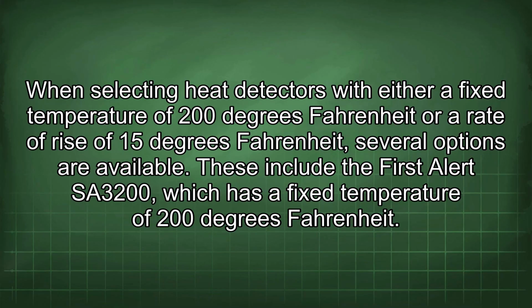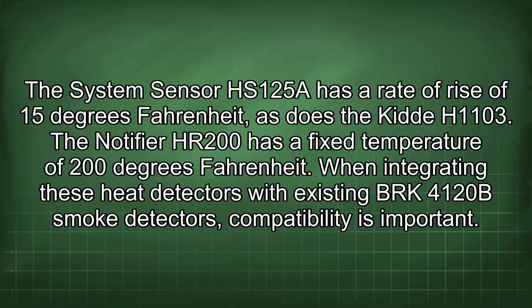When selecting heat detectors with either a fixed temperature of 200 degrees Fahrenheit or a rate of rise of 15 degrees Fahrenheit, several options are available. These include the First Alert SA3200, which has a fixed temperature of 200 degrees Fahrenheit. The System Sensor HS125A has a rate of rise of 15 degrees Fahrenheit, as does the Kidde H1103. The Notifier HR200 has a fixed temperature of 200 degrees Fahrenheit.